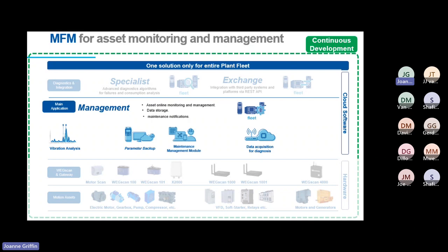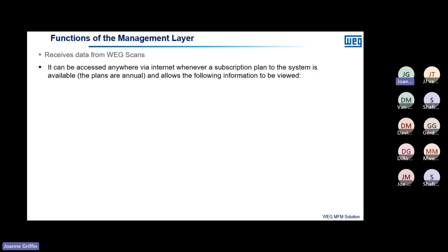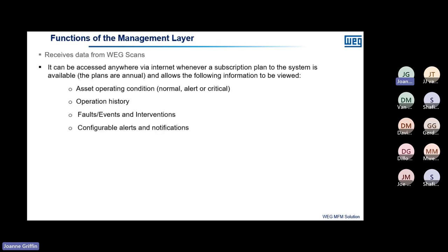The management software performs asset online management, data storage, maintenance reports, and provides intuitive dashboards. Its functions include receiving data from the sensors and allowing you to set asset operation condition thresholds — the level at which you want to be notified whether the asset is normal, warning, or critical. You can configure these yourself. People with experience with their own machines will know how to set the levels at which they should receive these notifications.